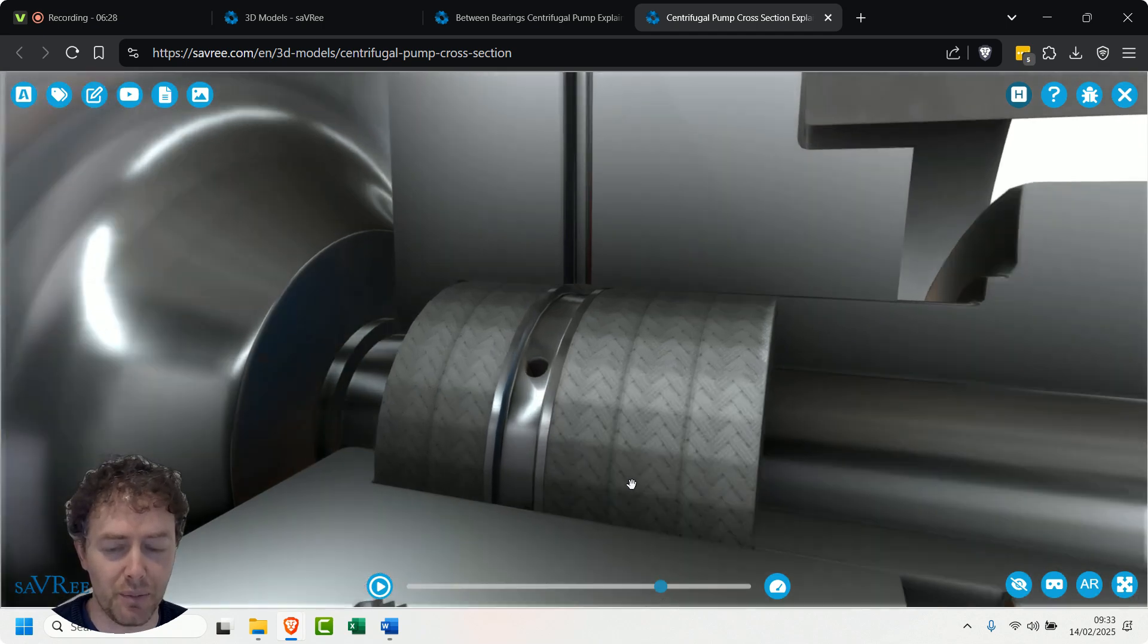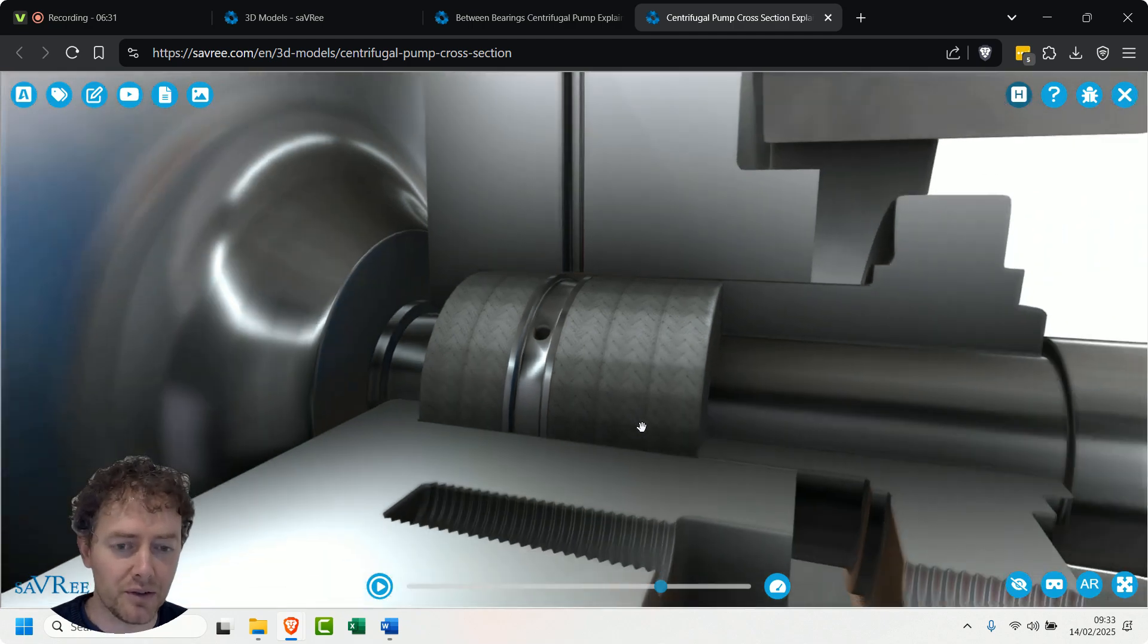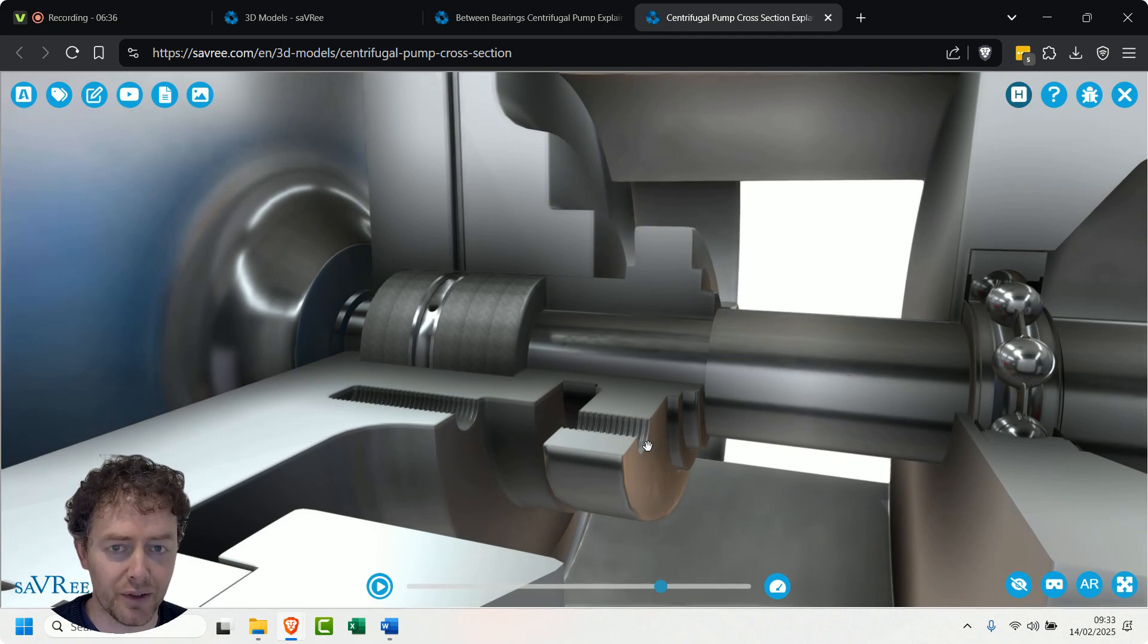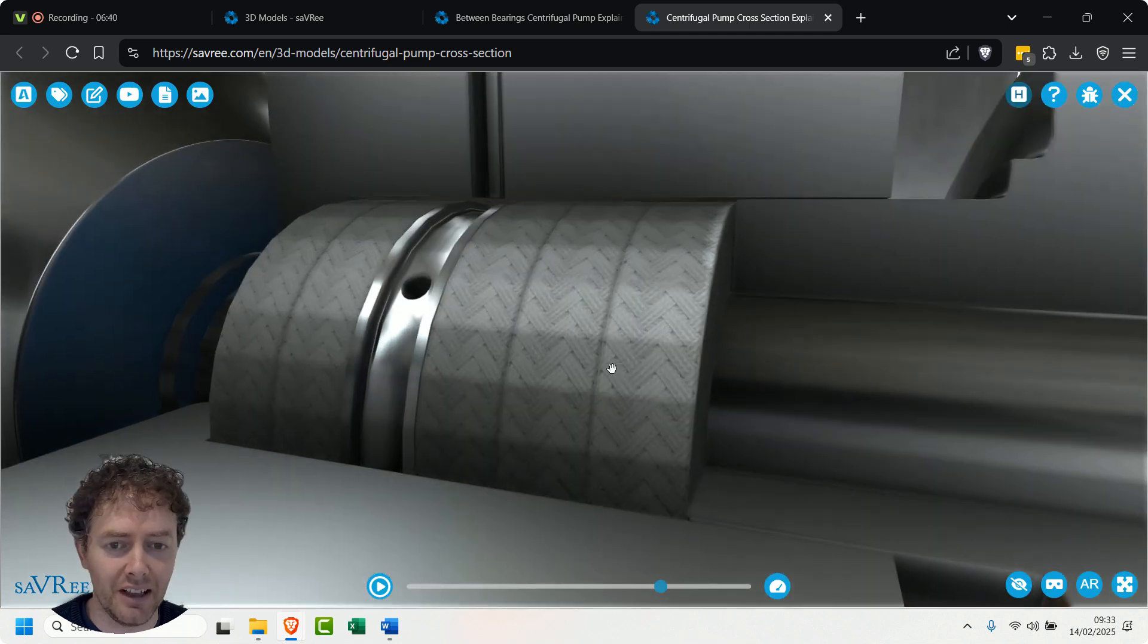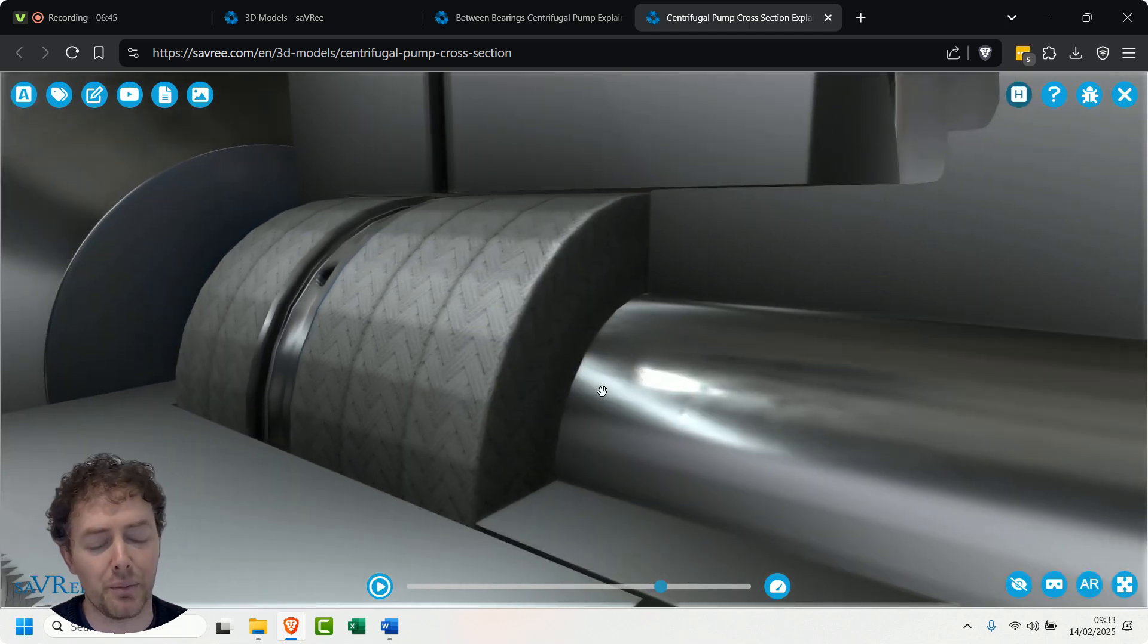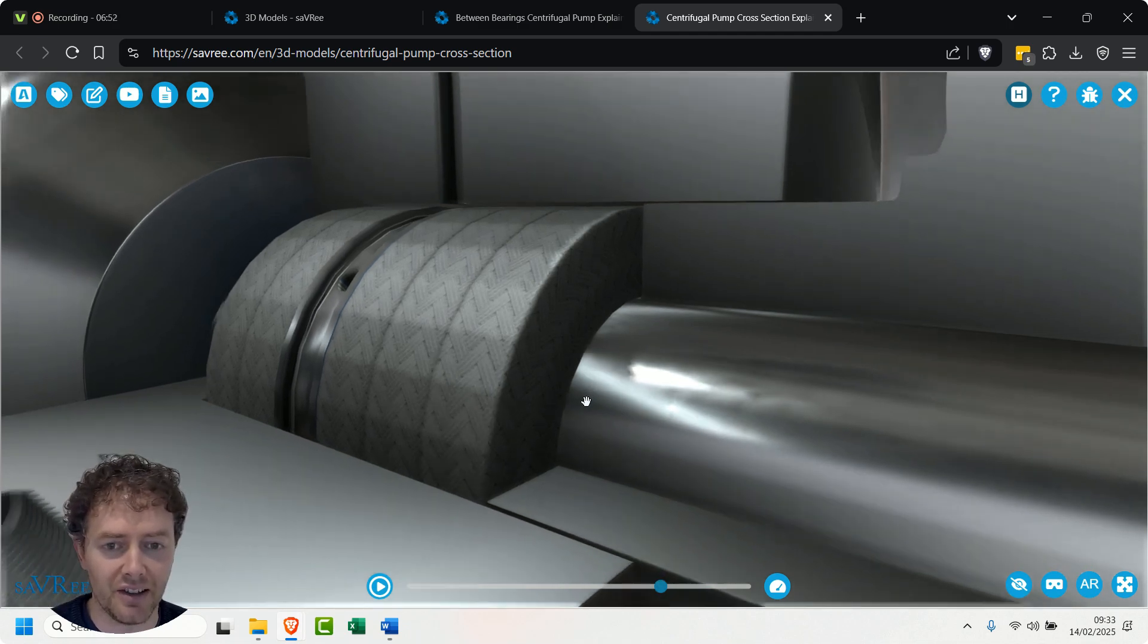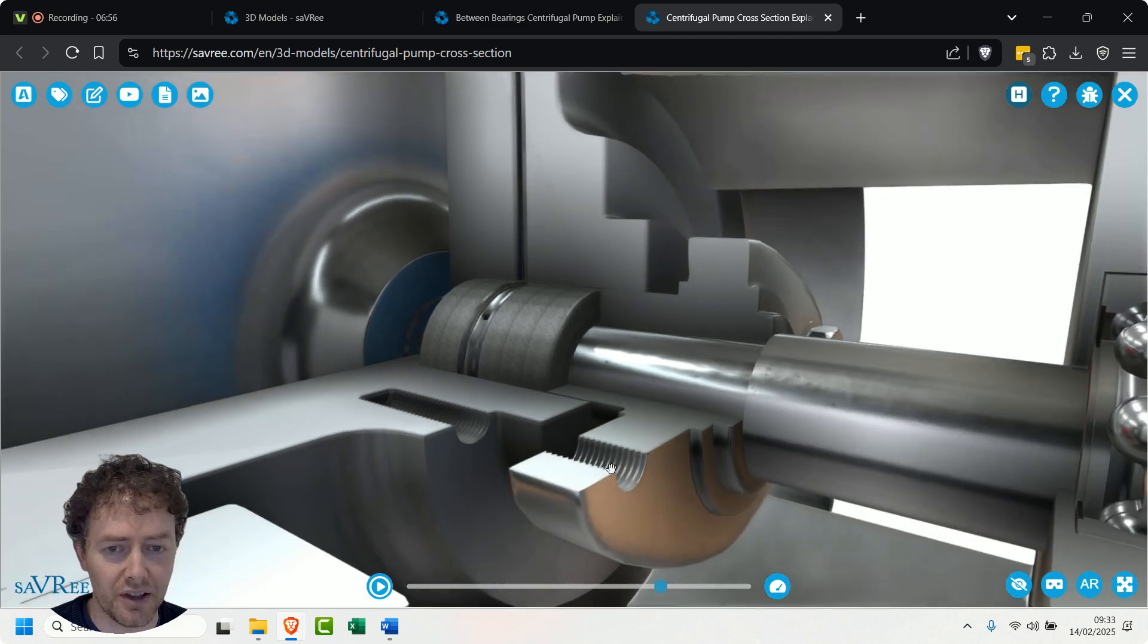The problem is with packing, when you're trying to maintain the pump, people over-tighten the follower, and what that does is it actually crushes the packing. And there's only one way for the packing then to go - it's to press hard up against the shaft. And when it presses hard up against the shaft, what you'll find is that it wears the shaft, so you'll get wear on the shaft, you'll get excess heat, and then you'll have to continually tighten up the follower to stop the leakage.